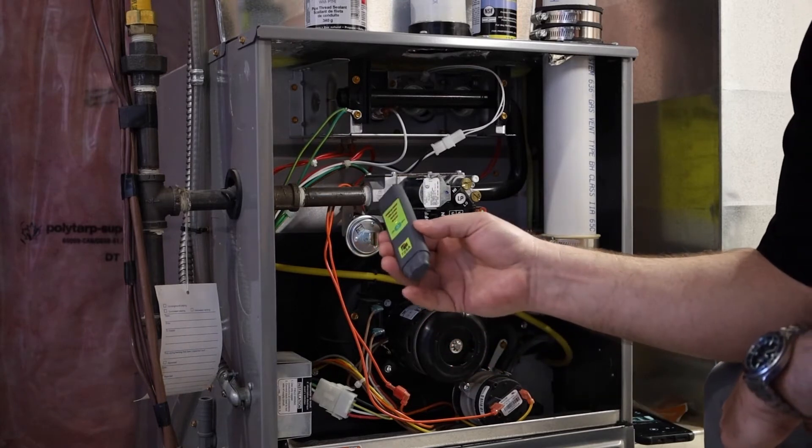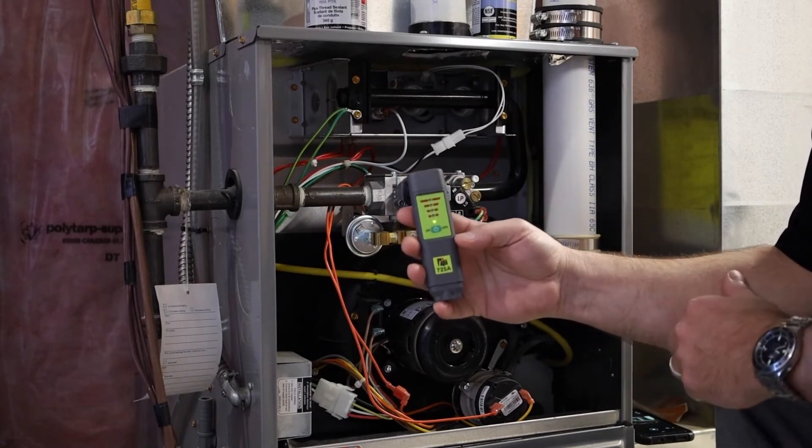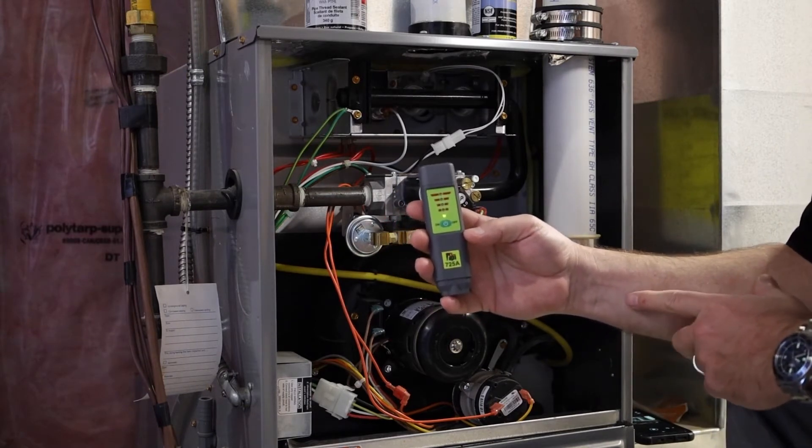I'm just going to move this over towards my suspected leak and there it goes. Very small leak, so we're actually under 500 parts per million.